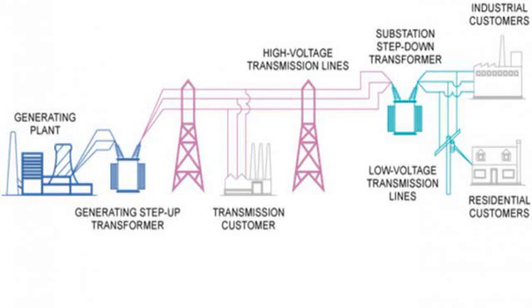Restoring power after a wide area outage can be difficult, as power stations need to be brought back online. Normally, this is done with the help of power from the rest of the grid. In the total absence of grid power, a so-called black start needs to be performed to bootstrap the power grid into operation. The means of doing so will depend greatly on local circumstances and operational policies. But typically transmission utilities will establish localized power islands, which are then progressively coupled together to maintain supply frequencies within tolerable limits. During this process, demand must be reconnected at the same pace that generation is restored, requiring close coordination between power stations.